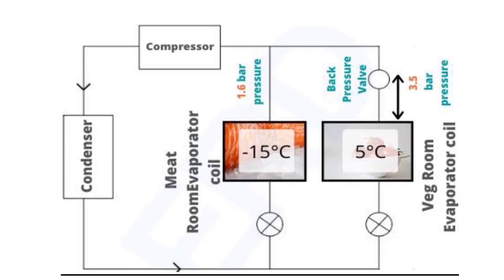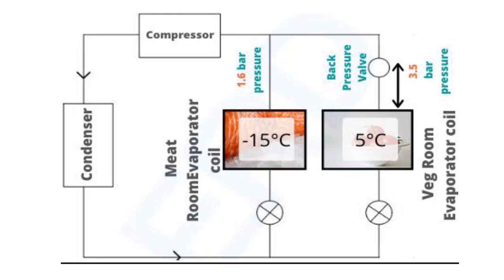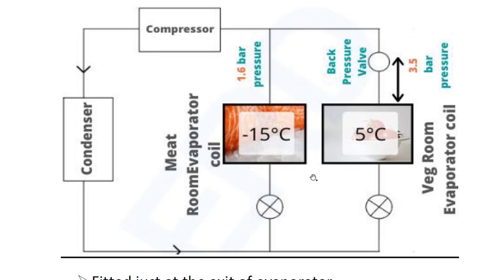First, let's take a look at the position. Here is a block diagram of the refrigeration system. We are dealing with two rooms: the meat room and the veg room. It is a multi-room system, and the back pressure valve is only found in a multi-room system. In the block diagram you can clearly see the condenser, compressor, evaporator, and the back pressure valve fitted at the veg room.